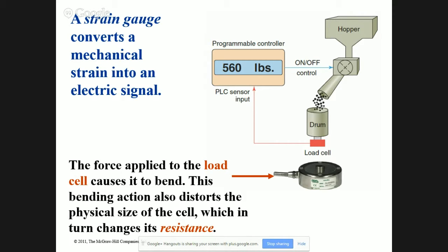Strain gauge. Load cells. Load cells typically use millivolts. Basically, it's a semiconducting material that whenever you bend it or stretch it, like a metal, it produces a small amount of voltage. And then we read that with some kind of transmitter that's close to the load cell because we get a voltage drop, right? So we gotta have it close. There's a listing on them, and they gotta be within 2 or 3 foot. And then we change that over to probably a 4 to 20 milliamp signal and send it on to our PLC.